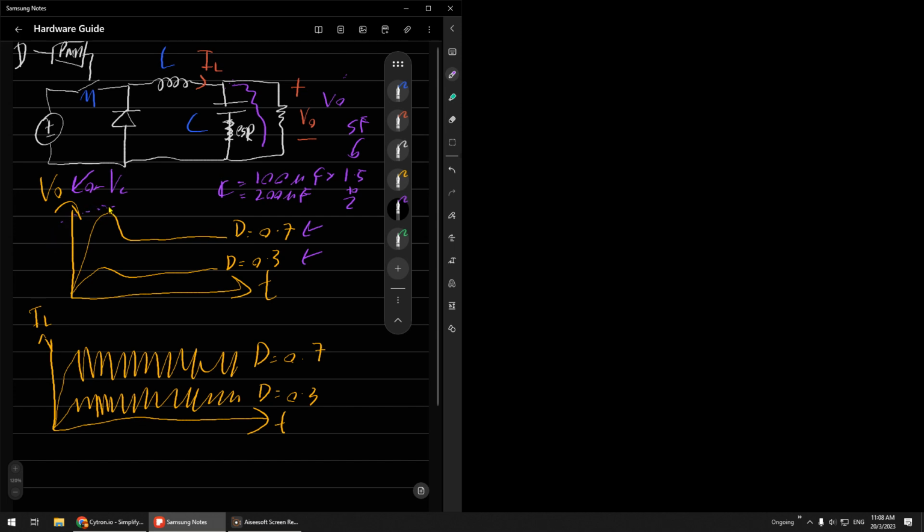So you have to look at this voltage. For example, this one is maybe 70 volt, this one is 100 volt. You have to look at this point, not the normal operation steady-state voltage, but the maximum peak voltage. So your voltage rating should be 100 volt, and better to multiply by a safety factor of around 1.5 to 2. For this case, it should be 150 volt.